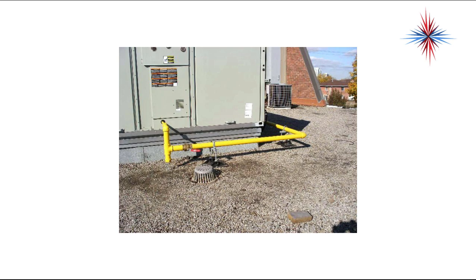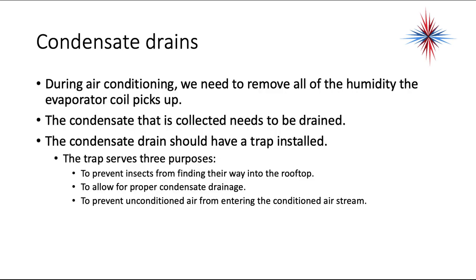During air conditioning, we need to remove all of the humidity the evaporator coil picks up. The condensate is collected and needs to be drained. The condensate drain should have a trap installed. The trap serves three purposes: it prevents insects from finding their way into the rooftop unit, allows for proper condensate drainage, and prevents unconditioned air from entering the conditioned airstream.